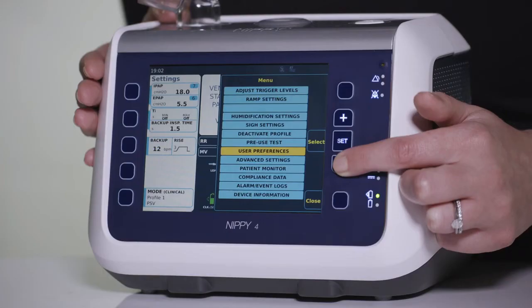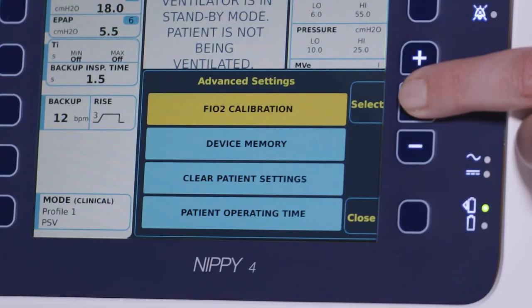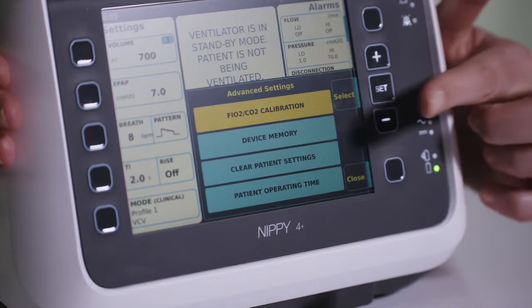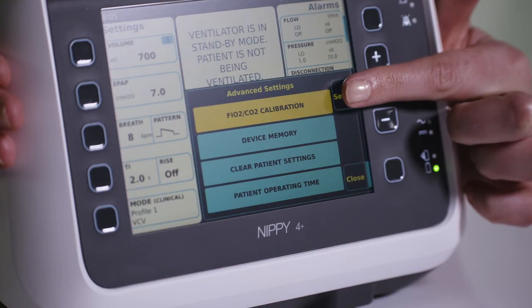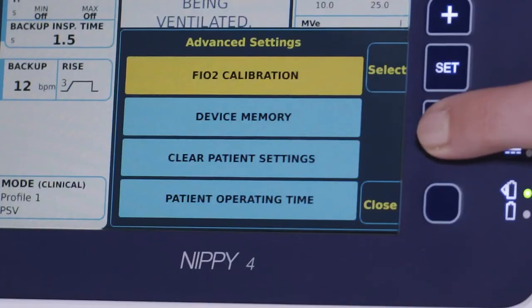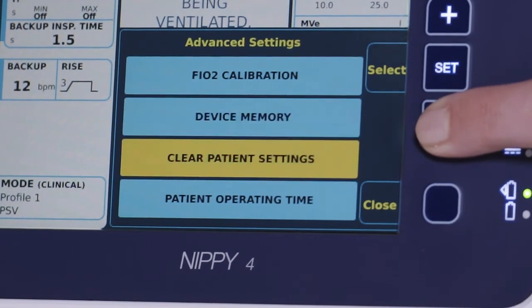The Advanced Settings section contains the following items: the FiO2 calibration, the end tidal CO2 sensor calibration, which is for the NIPPY 4 Plus only, device memory functions, clear patient settings if you want to return to the default device settings, and patient operating time reset if you are setting up a new patient on the ventilator.